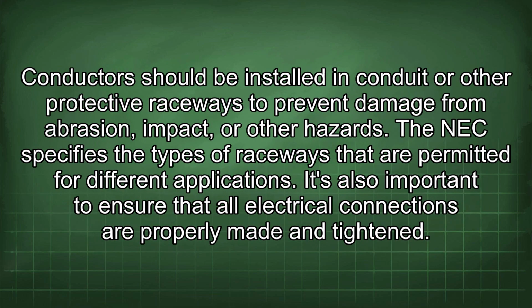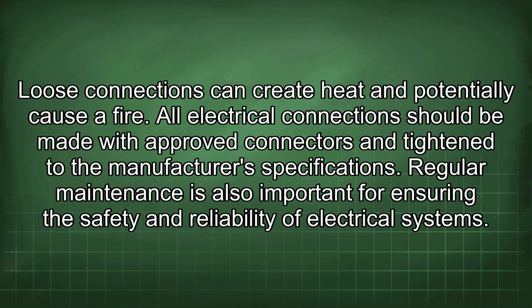Another common mistake is failing to properly protect the conductors from physical damage. Conductors should be installed in conduit or other protective raceways to prevent damage from abrasion, impact, or other hazards. The NEC specifies the types of raceways that are permitted for different applications. It's also important to ensure that all electrical connections are properly made and tightened. Loose connections can create heat and potentially cause a fire. All electrical connections should be made with approved connectors and tightened to the manufacturer's specifications.